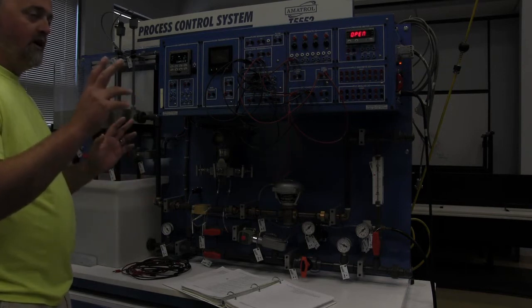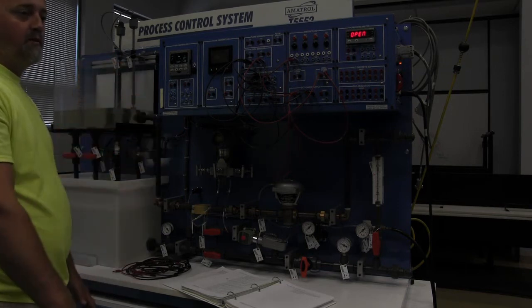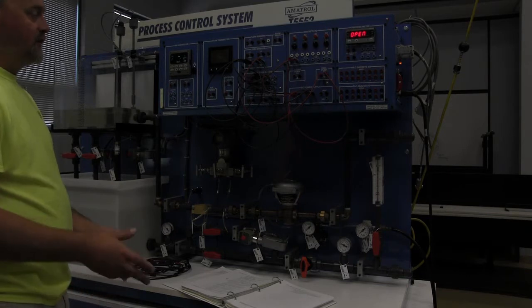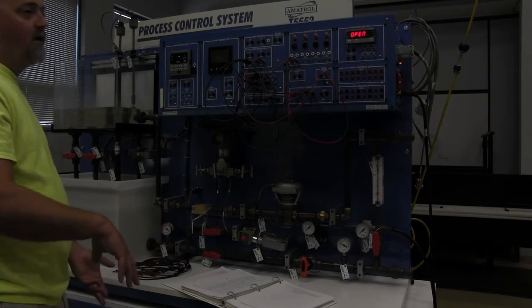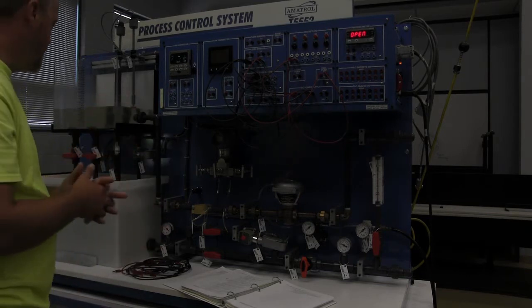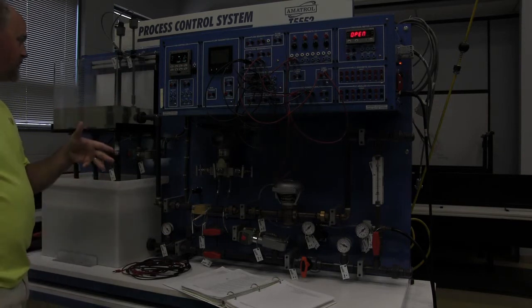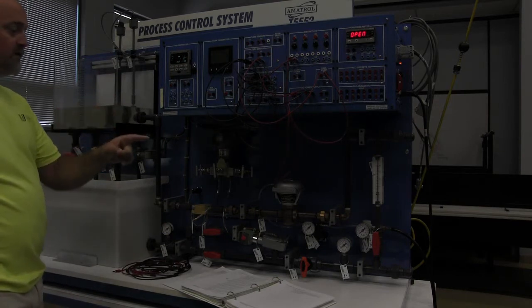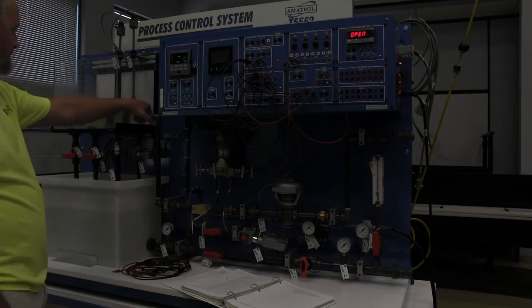In a pump down situation, you would have it just opposite. When both of them are on, it would turn the pumps on and pump it down until both of them are off. If you wanted to fill a tank, when both of them were off, you would turn it on until both of them came on. So the process pump is currently running. Process pump just shut off because the second switch was made.